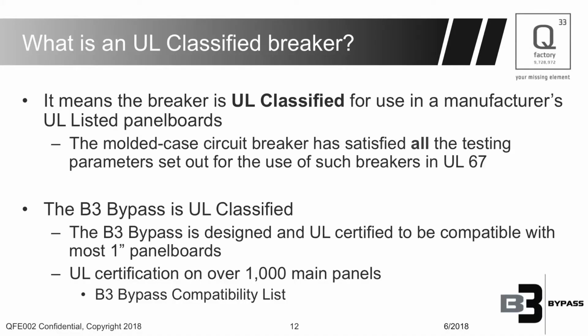So what is a UL classified breaker? The classified breaker program means that when it has a UL listing, it can be installed in other manufacturers' panel boards. So if you have a Schneider, a Square D, Eaton, GE, and we're listed on the compatibility list, then the B3 bypass can be installed in that main panel. It also means that the breaker has satisfied all the testing parameters for a typical circuit breaker. We are compatible with panels that accept 1-inch main breakers and 1-inch stab-in breakers. It will not work with panel boards that accept 3/4-inch breakers. Today, we are allowed to be installed in over 1,000 different main panels.